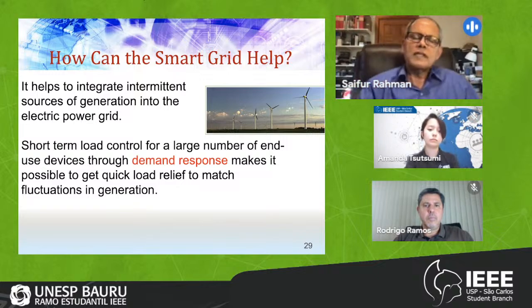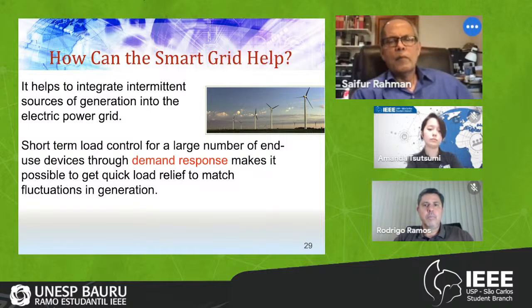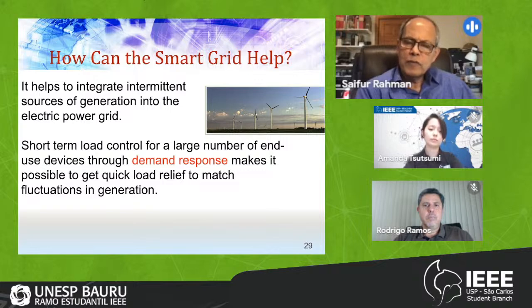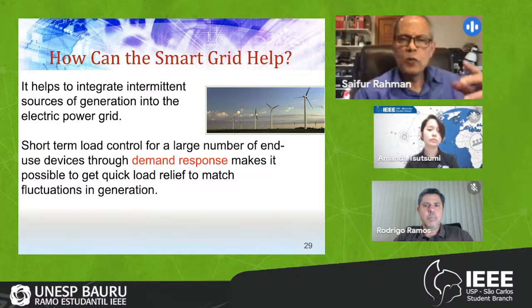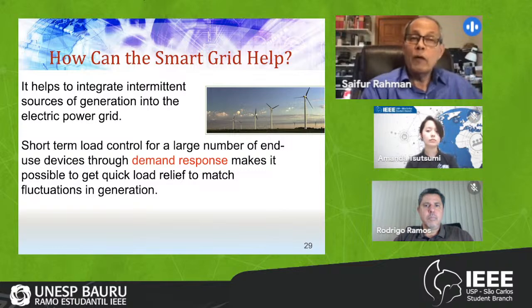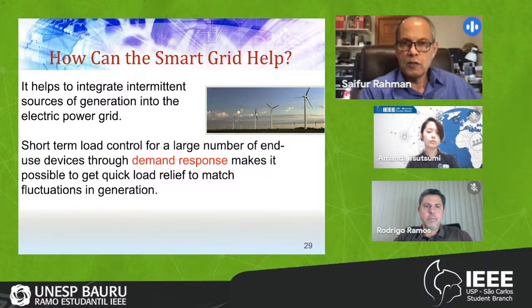Take an example, let's say a university campus with many buildings, and every building is a smart building. You can change the thermostat setting, change the light intensity, turn some fans off. The whole campus, with so many buildings, can save a few megawatts for a minute or two. In that case, when your wind and solar are fluctuating, you don't need to depend on all the battery backup for situations where wind and solar are out or not available for a few minutes.